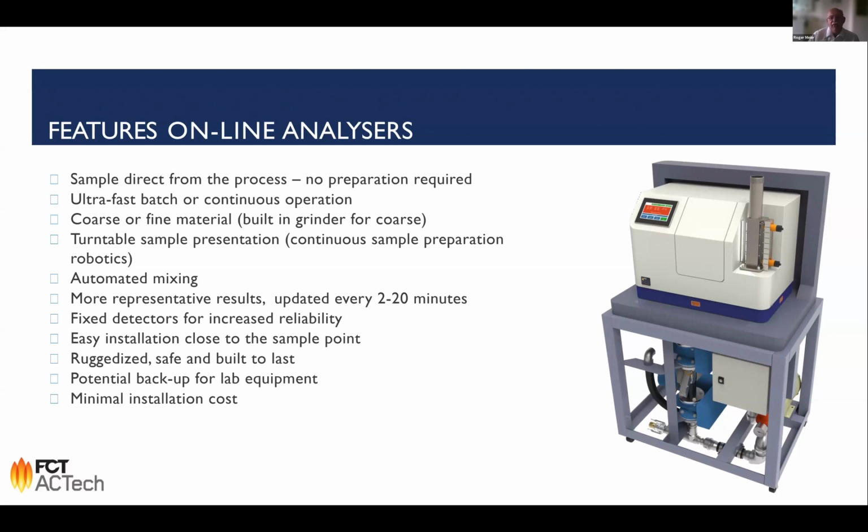Also, the systems come fully calibrated to you. The installation time is usually in the order of magnitude between 2 and 3 days, including a basic training. The whole equipment is or can be covered with a thing we call an igloo. It's a ruggedization kit to protect it against mechanical attacks, heat, and moisture. The intention is mainly to use it for online analysis, but of course, via the software, you can take it out of the automation and use it also as a backup for emergency for your lab equipment.